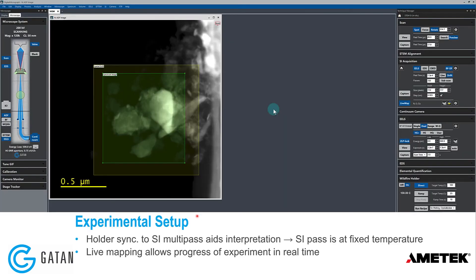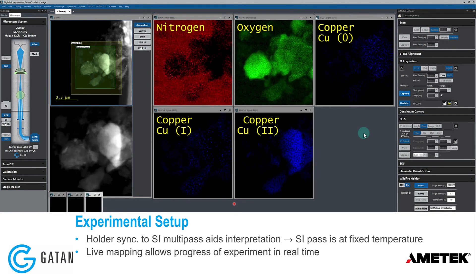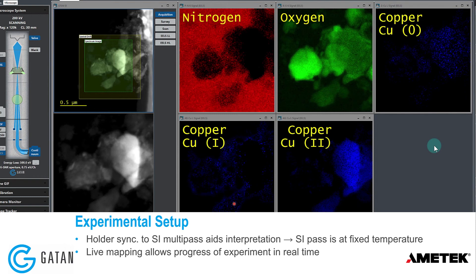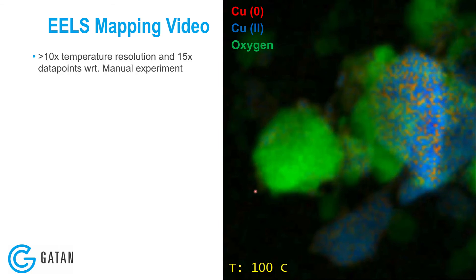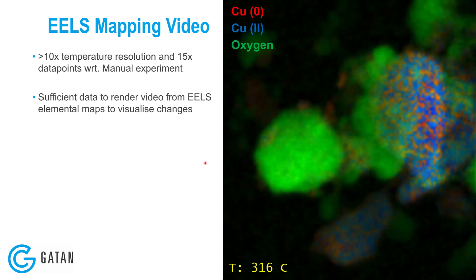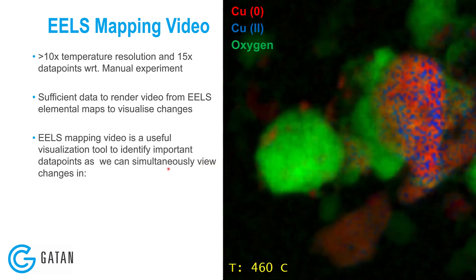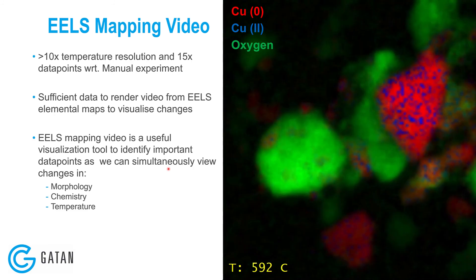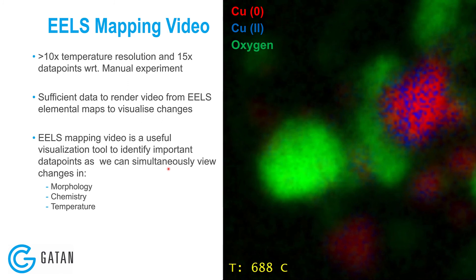In the experiment, multi-pass acquisition begins after hitting capture. Having the holder synchronized to the multi-pass method greatly aids data interpretation, as each spectrum image pass is acquired at a fixed temperature. Live mapping shows elemental maps and oxidation state maps evolving in real time, helping visualize what's happening during the experiment. This produces video output with more than 10 times the temperature resolution and 15 times the number of data points compared to the manual experiment, allowing simultaneous visualization of changes in morphology, chemistry, and temperature.